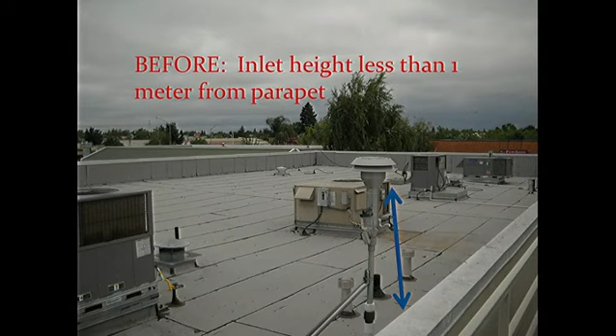Another siting issue. How high does an inlet have to be from the ground for most instruments and probes? I heard a bunch of different answers. Minimum of 2, no greater than 15. So if you're on a 3-story building, you're cutting it close. So just be aware there's a siting limit. This is something that we saw out in the middle of nowhere, and this is how they fixed it. Be careful, because this supervisor told them to raise it in inches, and we are dealing in metric. So just be careful about that.